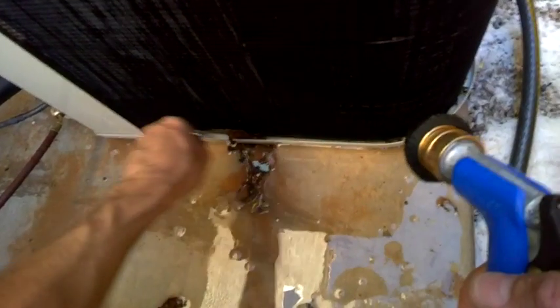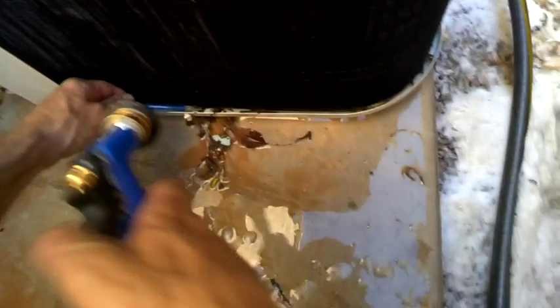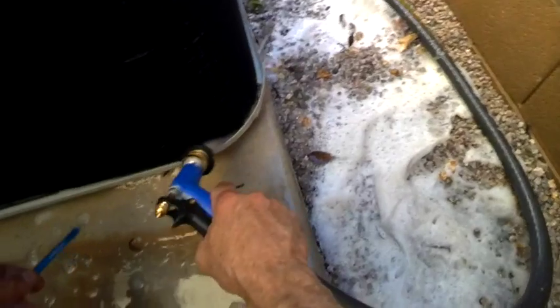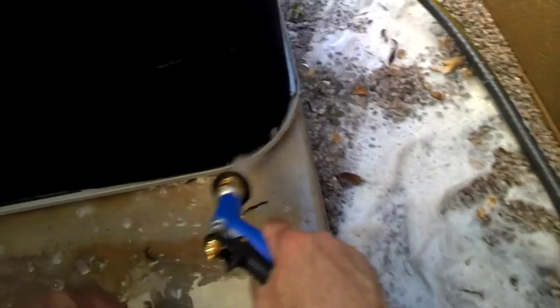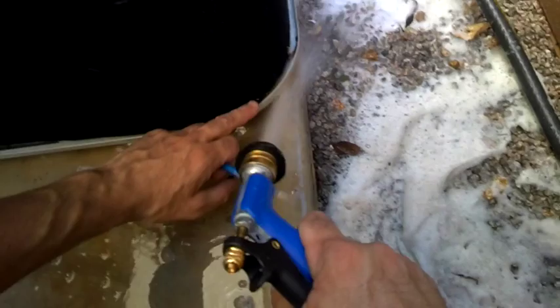With this type of unit, what goes on is the rocks get caught up under the coil right here. It's very important to clean those rocks out because over time the vibration will cause the coil to vibrate on those rocks, creating leaks. If you keep the rocks out of this machine and keep it clean, this coil will last a long time.